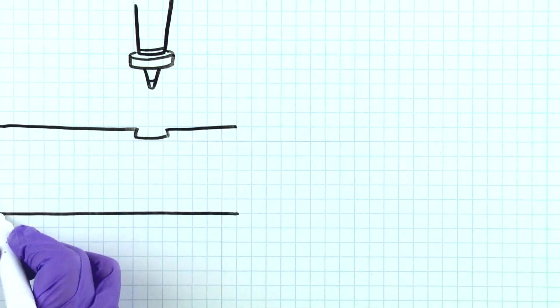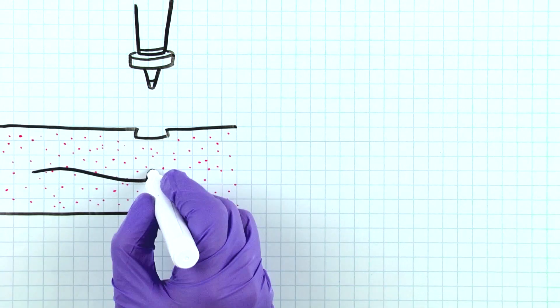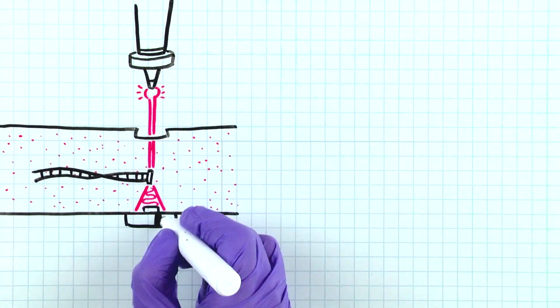A really cool thing about fragment analysis is that you can multiplex, meaning you can have multiple fragments in a reaction well going through the same capillary. The smaller fragments usually run faster and the bigger ones run slower. Shortly before reaching the positive electrode, the fluorescently labeled DNA fragments separate by size, moving through the path of the laser beam.